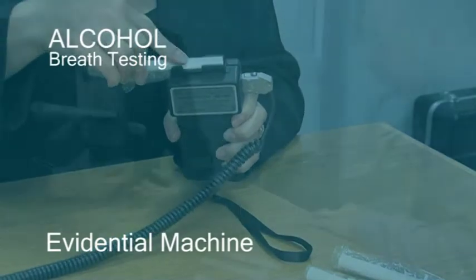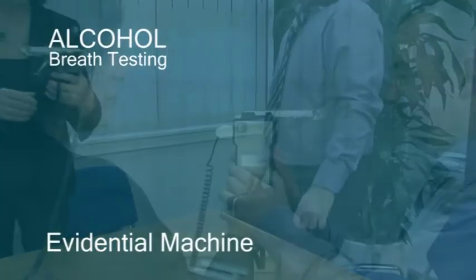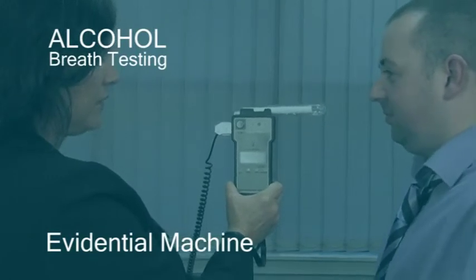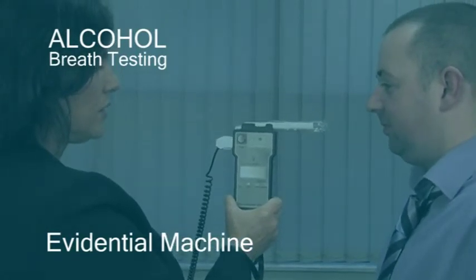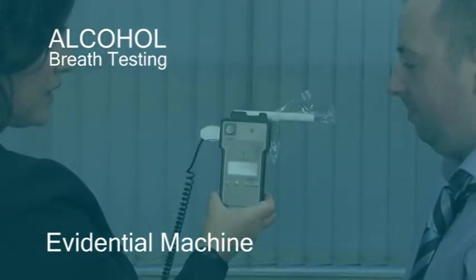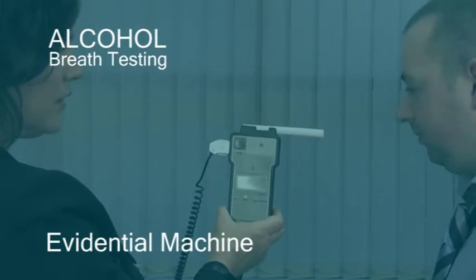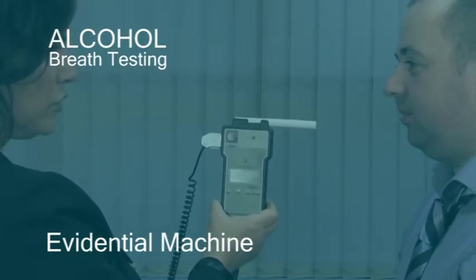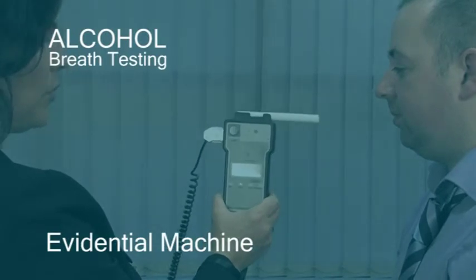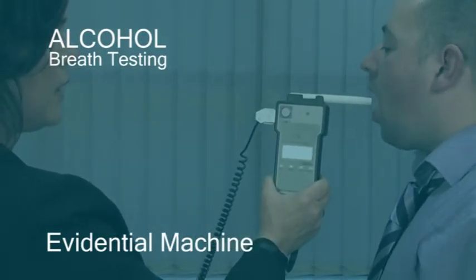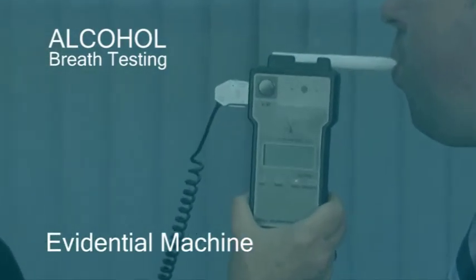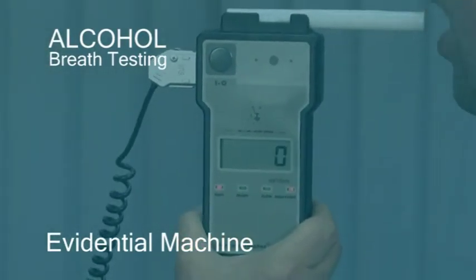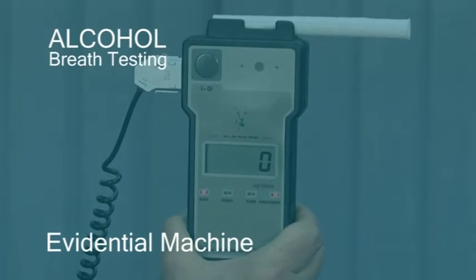Ask the individual to stand up with their hands by their sides and explain that you will hold the machine. They should not touch it. Explain that they need to take a deep breath and then blow slowly and steadily into the mouthpiece until you tell them to stop. Remove the wrapper from the mouthpiece and, holding the machine at a comfortable height for the donor, not for you, ask them to provide a breath specimen. Encourage them by saying, keep blowing, until you get the indicator from the machine that the specimen has been taken.